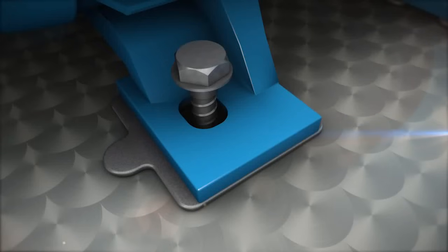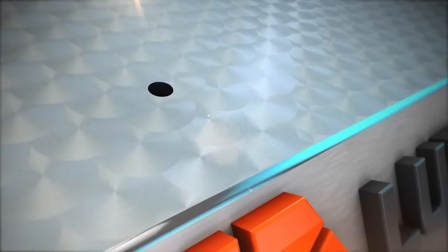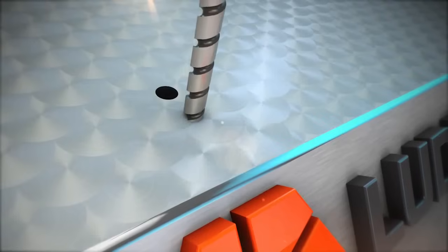Common solutions to being bolt bound are increase the bolt hole size in the machine foot, reduce the shank diameter of the anchor bolt, or drill and tap a new hole in the base.